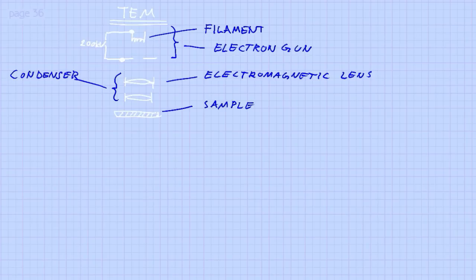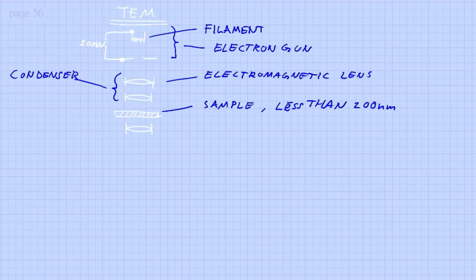Beneath the condenser we place the sample. One drawback with transmission electron microscopy is that the sample needs to be transparent to electrons, which means it must typically be less than 200 nm in thickness. Getting down to 200 nm is very challenging, so you usually need to use techniques such as electropolishing or ultramicrotoming. Beneath the sample is the objective lens, which does the focusing and is the most important lens — any error in this lens will be magnified by all subsequent lenses, so it must be set up correctly.